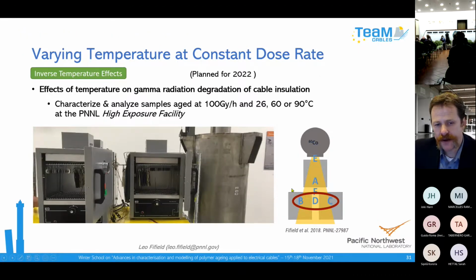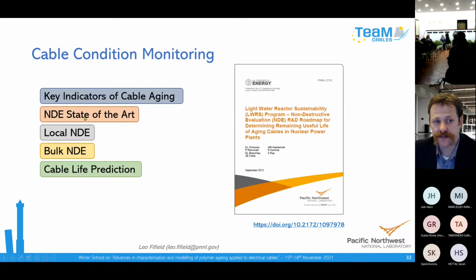What we're planning to study in the coming year is the so-called inverse temperature effect. We have exposed cable samples in our facility here at PNNL with a cobalt-60 gamma source. We exposed 3 different sets of cable samples at 3 different temperatures, all at a common dose rate: 60 degrees, 90 degrees and room temperature, all at 100 gray per hour. We're going to compare the effects of a series of different doses on those materials at those different temperatures to look at this inverse temperature effect.